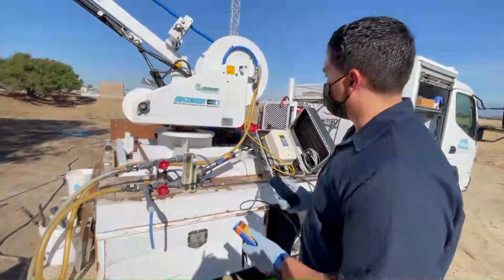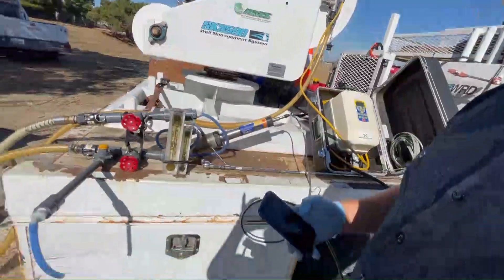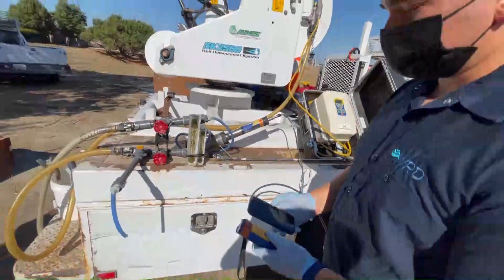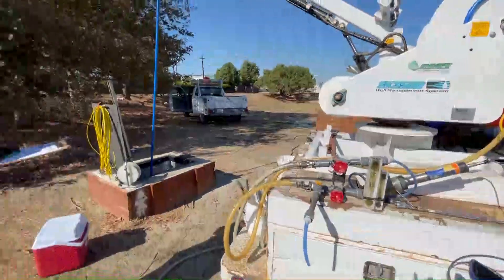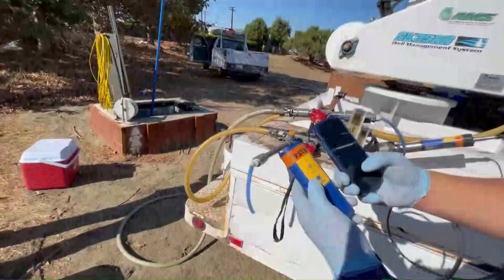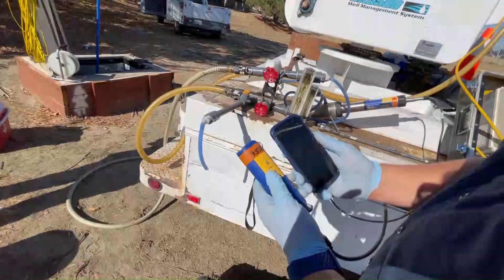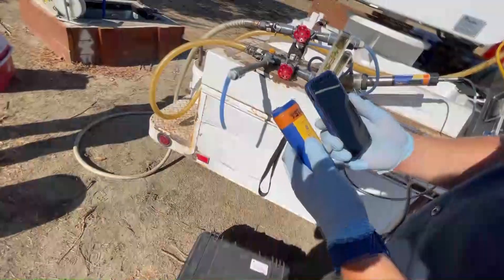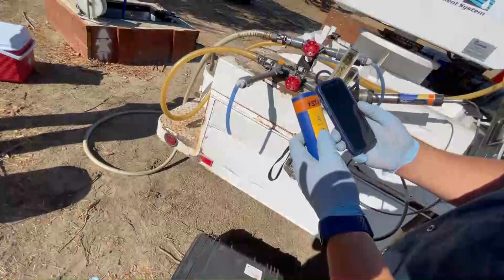While Peter figures out how long our purging period is going to be, I'm going to start looking at the water quality of the water that we're pumping out. We communicate with this water quality meter via a Bluetooth device and an application on a mobile phone. I'll sync them together — this does take about a minute — and now I'm connected to our device and I can click on live readings to see various water quality parameters in real time, refreshing every two seconds.